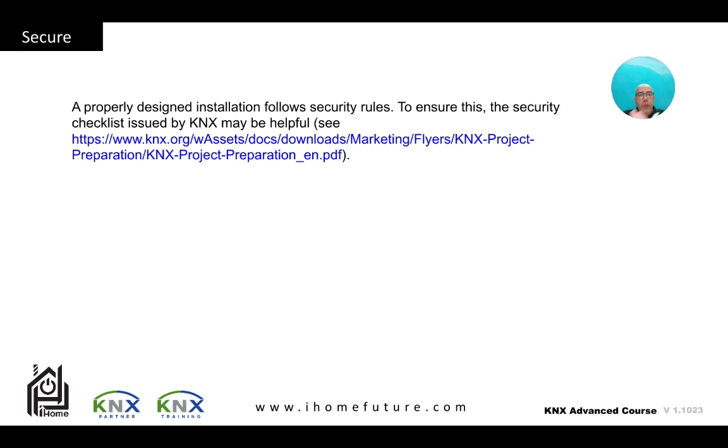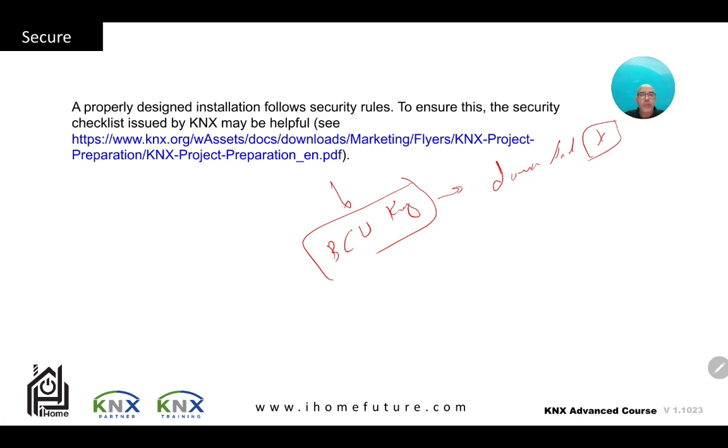One more thing: if you want to secure your KNX installation, then you should also use the BCU key. The BCU key is the key that, if I'm using it, then download on the bus is not possible. So my devices are now almost read only. I cannot download to the bus until I use the BCU key. So the whole framework is ETS password, and BCU password or BCU key.